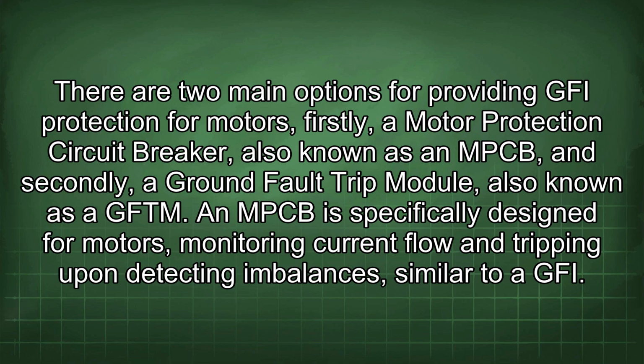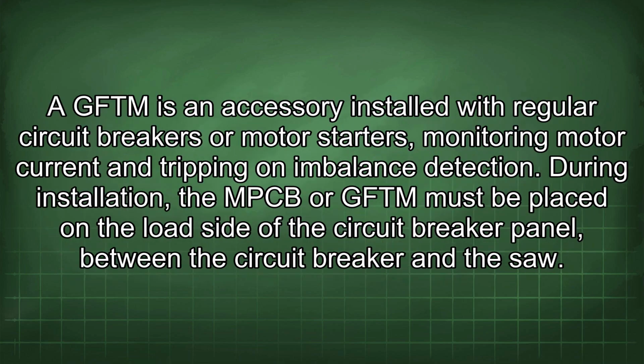Firstly, a motor protection circuit breaker, also known as an MPCB, and secondly, a ground fault trip module, also known as a GFTM. An MPCB is specifically designed for motors, monitoring current flow and tripping upon detecting imbalances, similar to a GFI. A GFDM is an accessory installed with regular circuit breakers or motor starters, monitoring motor current and tripping on imbalance detection. During installation, the MPCB or GFDM must be placed on the load side of the circuit breaker panel, between the circuit breaker and the saw.